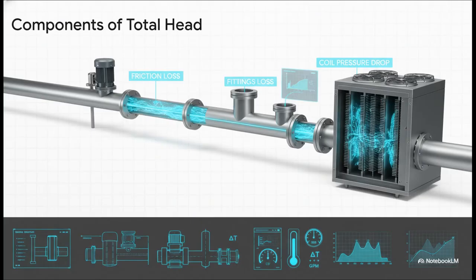So where does all this resistance come from? Well, it boils down to three main culprits. First, you've got friction from the water literally rubbing against the inside walls of the pipes. Second, you get turbulence and more friction from every single bend, T, and valve in the system. And third, there's a big pressure drop when you force the water through the tight, dense coils inside the cooling units themselves. And because this is a closed loop, static head is zero. We don't have to worry about lifting the water to a higher elevation.